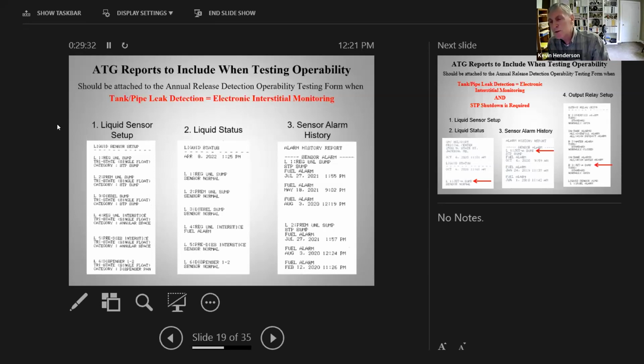And then the sensor alarm history report, of course, obviously is where you document that you actually did cause those sensors to go into alarm. If you know how Veeder works, you know that the alarm history reports will only capture the last 3 alarms of each type. So you see the L1, regular unleaded sump. That's the STP sump. There's the July 27, 2021, 1:55 timestamp. That date better match the date that you were there doing the annual operability test.